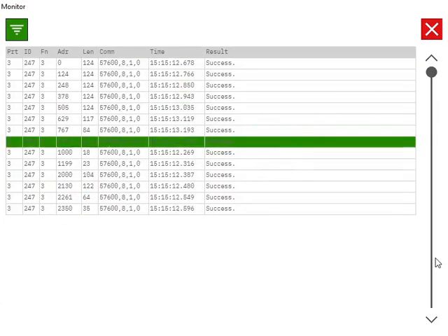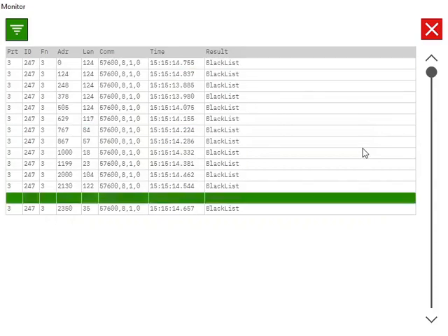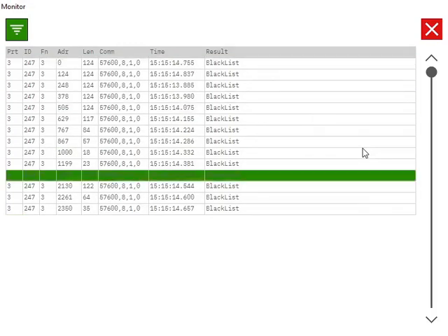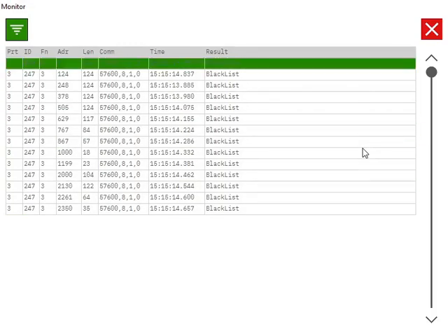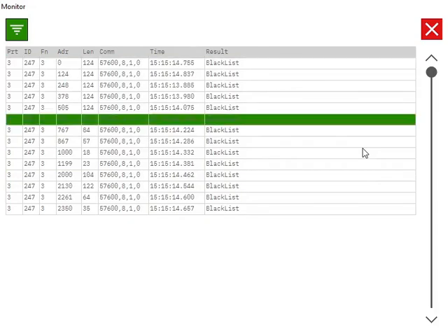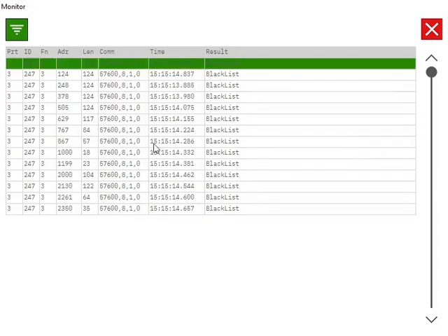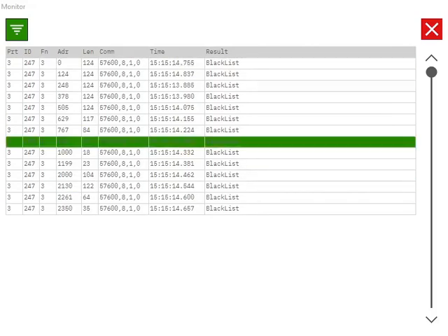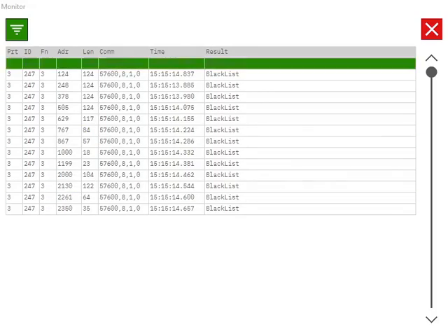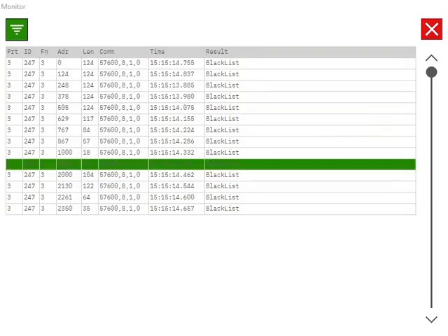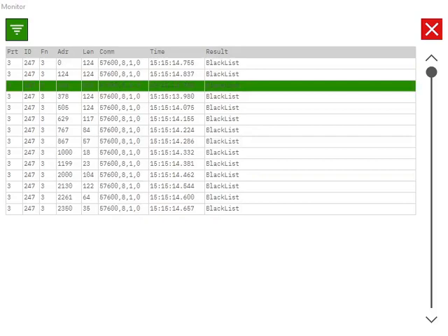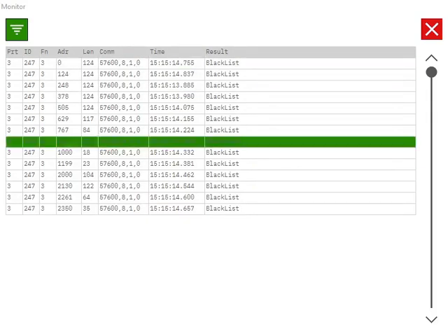In this example, Boiler 1 stops responding and timeout errors occur. After 10 consecutive read failures, NXTSD5 determines that a device's communications has failed. The requirement for 10 consecutive failures is used to filter out spurious comms errors. The device will then enter blacklist mode. In blacklist mode, only the device's first message is processed. If the first message is unsuccessful, the failed device's remaining messages are skipped.